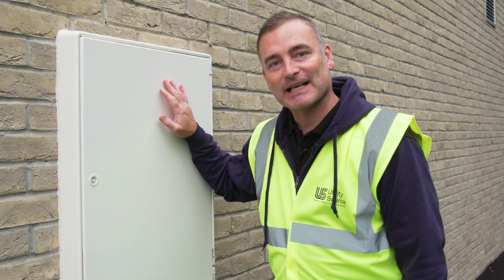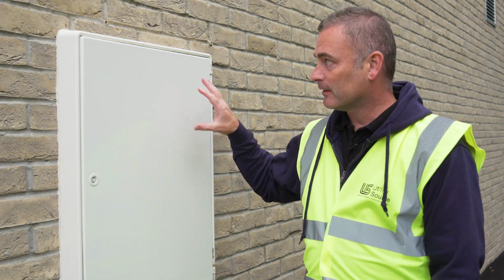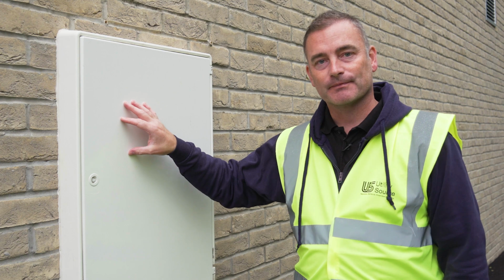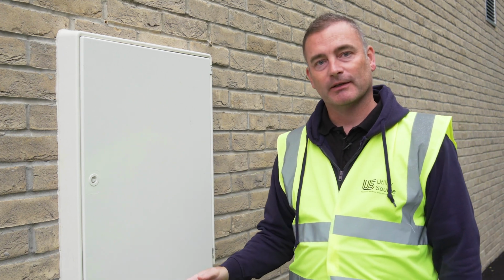When installing a three-phase supply, it's important to understand that you need to request a three-phase meter. So when speaking to the energy supplier, you need to pass on the MPAN number, you have to confirm that the supply is three-phase, and they'll probably ask you questions around the load that you've got allocated to your property. Finally, a point of note, this is a three-phase meter box. You'll see that it is much bigger than the domestic meter box that you've got on the side of your property at home.